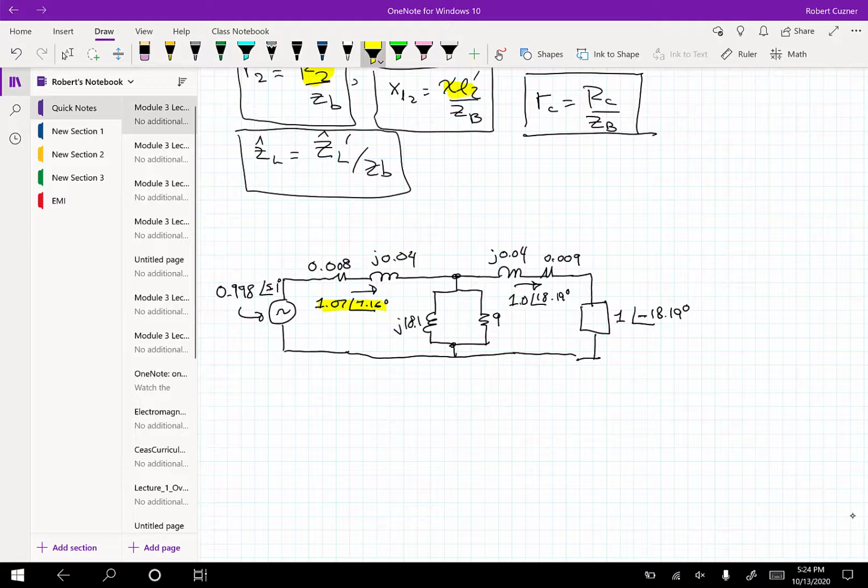because it's basically saying that I'm at a 7% overload of a rating. So I probably want to derate the transformer.